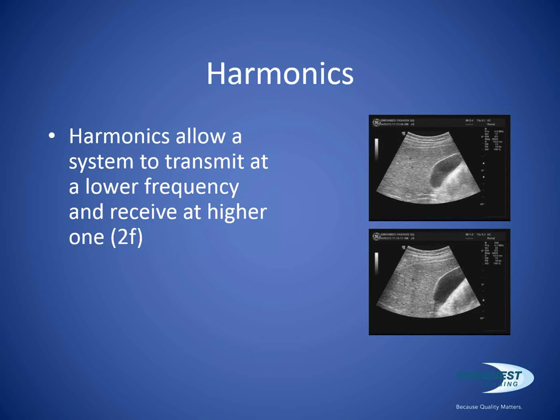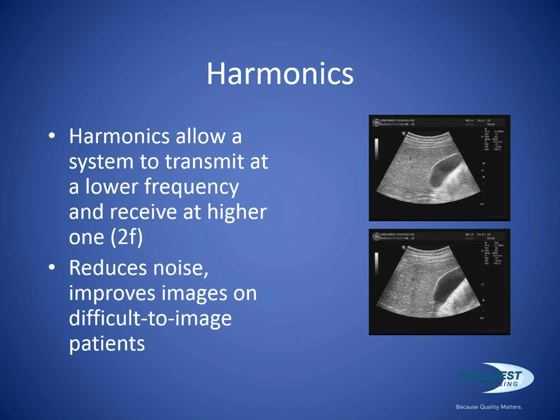If you look at this image here, what you're looking at is my gallbladder. The top one is using a primary frequency, and on the bottom one I turned on harmonics, and you can see the noise in my gallbladder up top is greatly diminished in the image at the bottom. Harmonics was developed mainly for difficult-to-image patients, but it's used pretty commonly these days. Most sonographers just default to using harmonics. However, depending on body type, it may or may not look good.